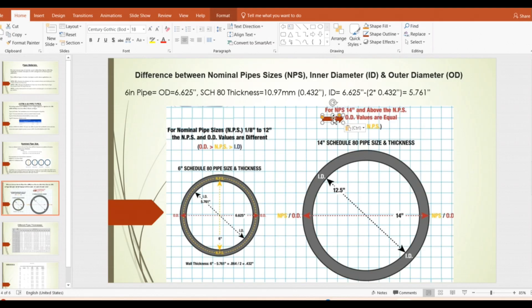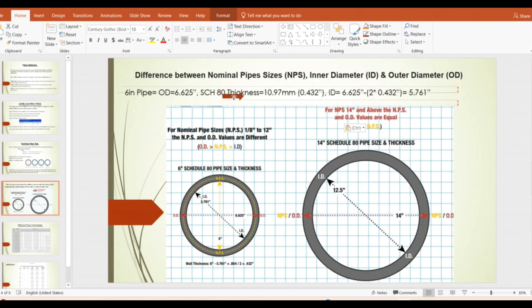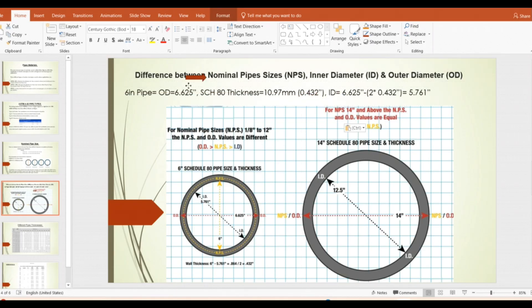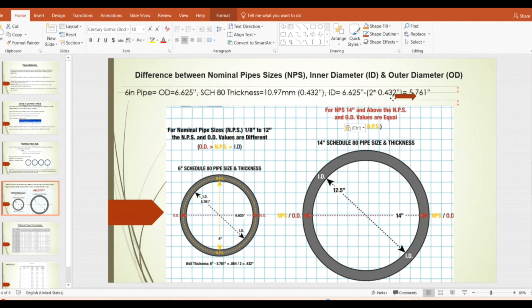Here is an example with a 6-inch pipe. The 6-inch pipe outer diameter from the table is 6.625 inches. For Schedule 80, the wall thickness from the table is 10.97 mm or 0.432 inch. The inner diameter equals outer diameter minus two times thickness, which gives 5.761 inches.